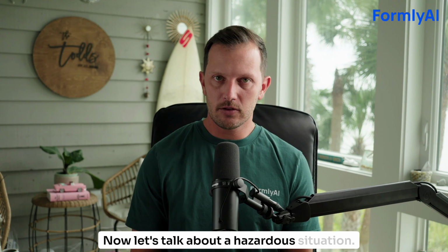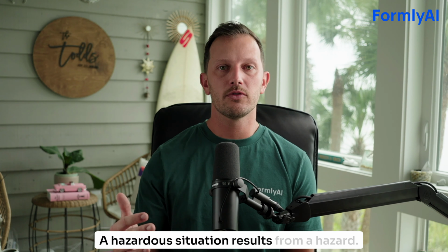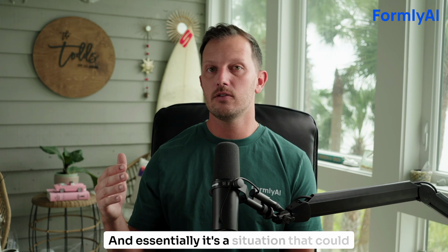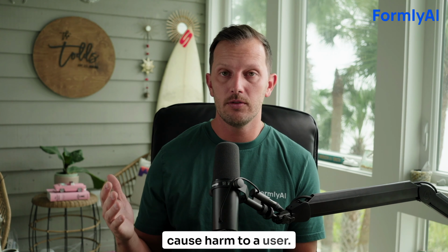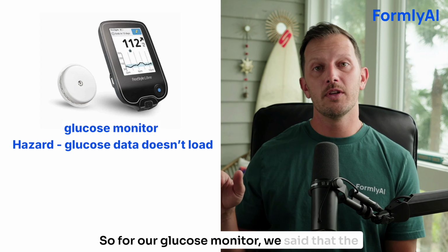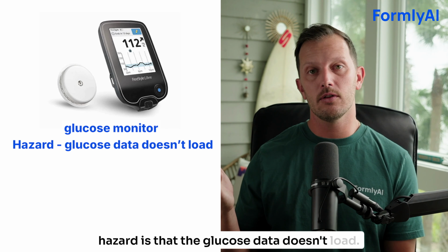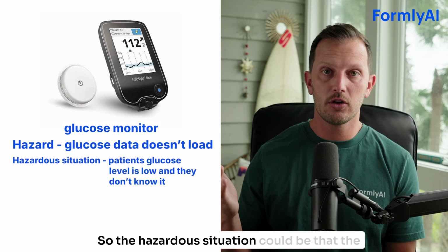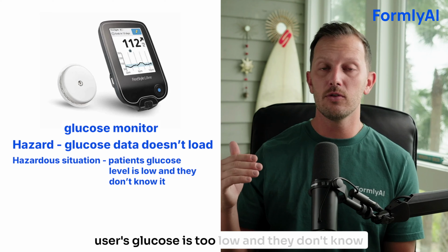Now, let's talk about a hazardous situation. A hazardous situation results from a hazard, and essentially it's a situation that could cause harm to a user. So for our glucose monitor, we said that the hazard is that the glucose data doesn't load. So the hazardous situation could be that the user's glucose is too low and they don't know it.